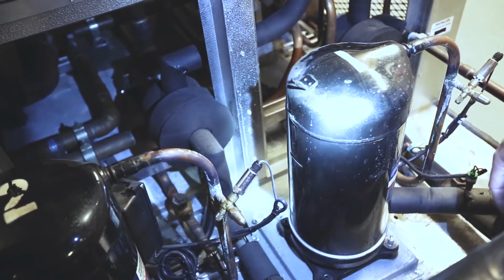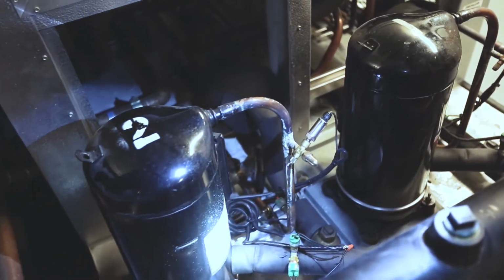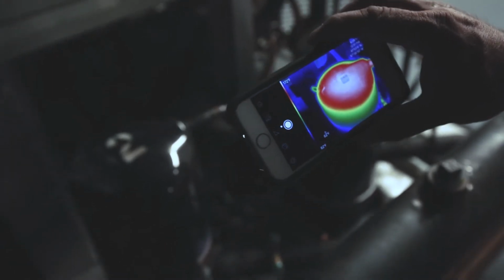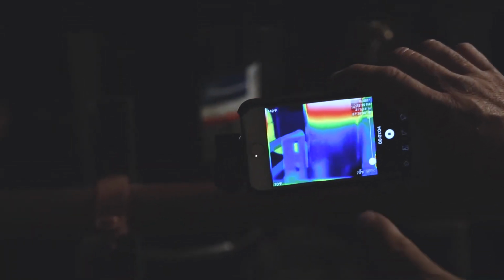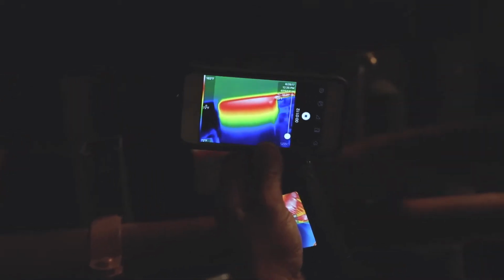Let's scan one of these compressors that are running. Look at the thermals on that compressor. You can see you're getting decent suction cooling. That's the bottom of your compressor where your suction enters, and here's where your discharge begins, out. Look at that band, nice and smooth.